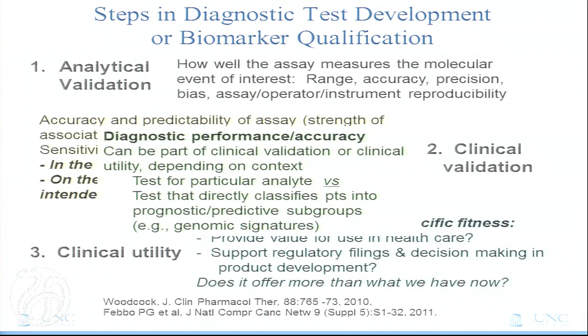There's an idea of diagnostic performance and accuracy that, depending on the test, could be part of clinical validation, or it could be part of clinical utility. For example, a test for an analyte like serum potassium — how well it detects serum potassium — would be part of clinical validation. A complex genomic test that has an algorithm giving a final result directly linked to, for example, treatment outcome with a particular drug in a patient population may, in fact, be part of the demonstration of clinical utility.